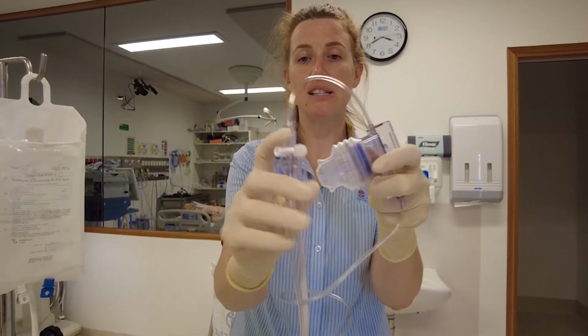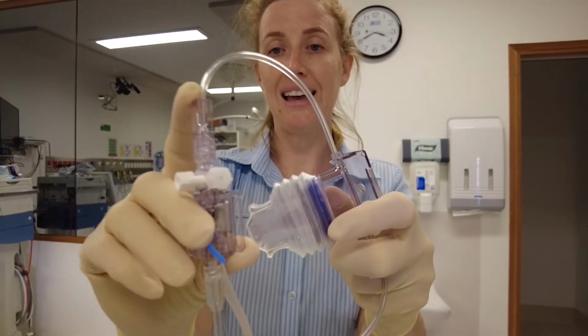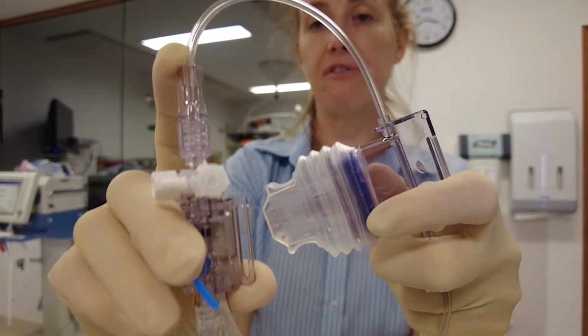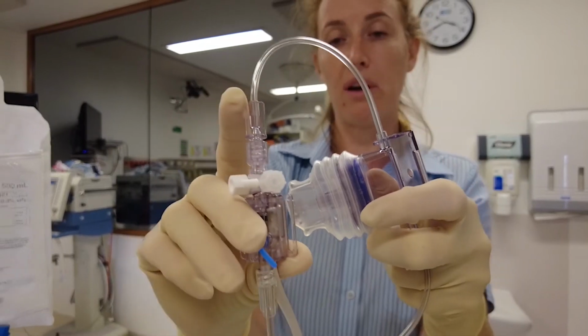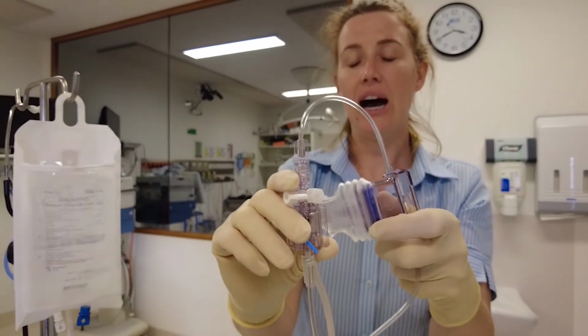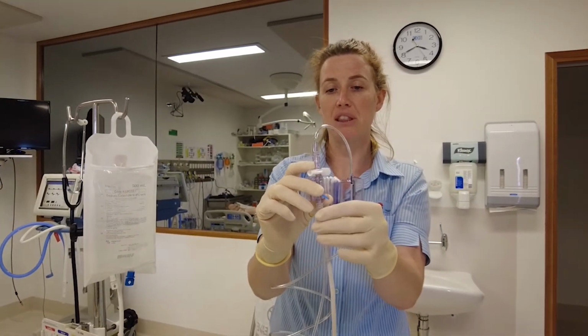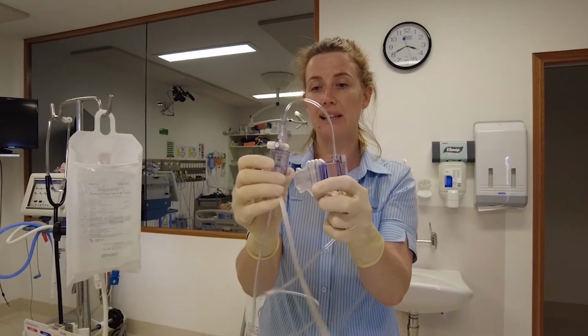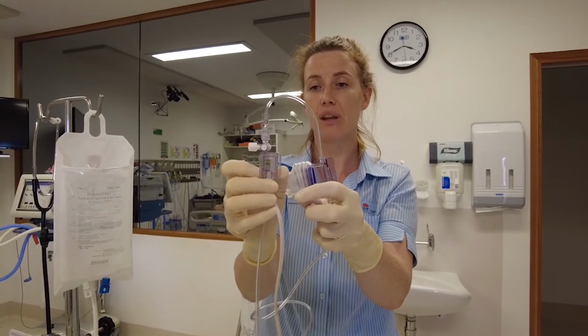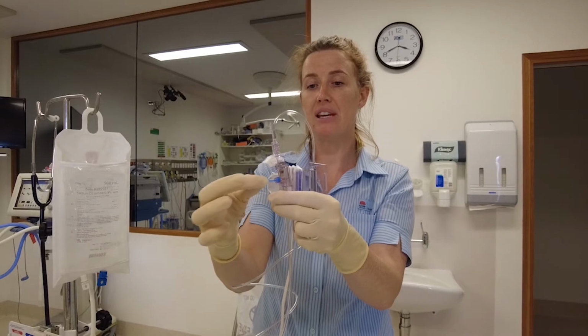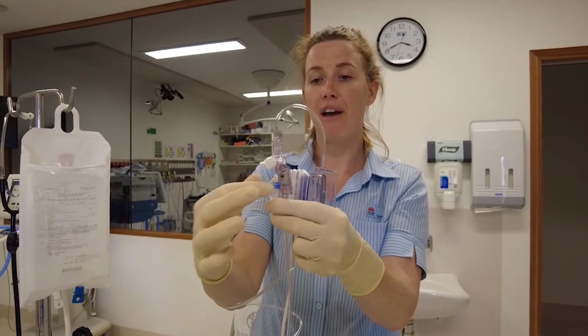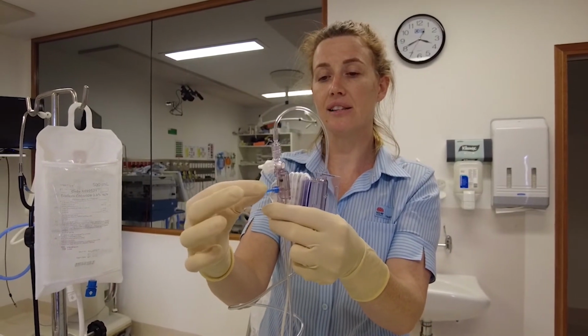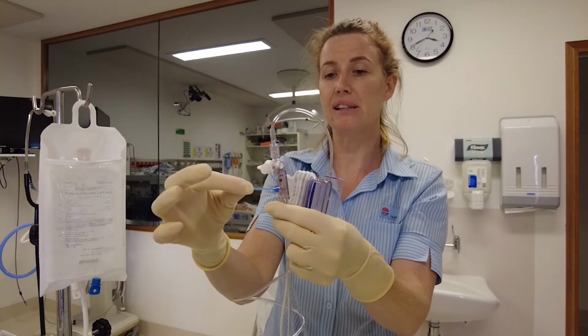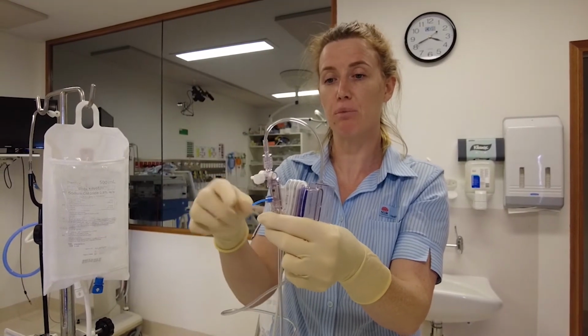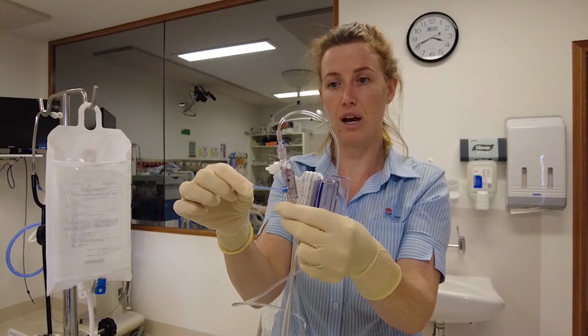This component here is the actual transducer. This is the bit that we need to zero to atmospheric pressure at the phlebostatic axis, or wherever we're monitoring blood pressure. This is the bit that we open, and you can see that's where all the electronics are in the back. Okay, and this little blue tab here, when I pull it, it opens a valve on the inside. It's called a fast flush tab. Basically, that's how we flush the line with the saline fluid that's going through the line.